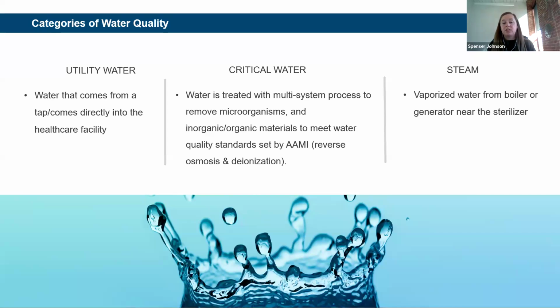Critical water is used for high level disinfection—that's the end process when you're treating these medical devices, that reprocessing step. It usually undergoes some sort of treatment, like a DI system or a reverse osmosis system. And then your steam is going to be your vaporized water from your boiler or generator near the sterilizer.